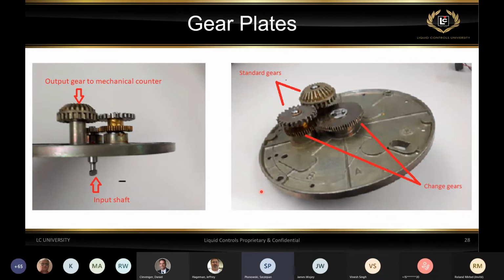If we look at a very simple gear plate picture, the gear plate, again, is a plate with a set of gears. On the bottom of that plate, you're going to see an input shaft, and that input shaft will generally engage with an adjuster, or some people call it a calibrator, micro adjuster. Then you have a set of gears that creates a specific output speed, and then you have an output gear, this little bevel gear, and this bevel gear will be engaged in most cases directly with the counter, with a similar bevel gear on the counter. Now, a gear plate has 2 gears. Again, in general, there are standard gears. That's the bevel gear, and you're going to see this silver gear. No, you can't see that part, but it will have the number 25 on the top. Those are considered standard gears, and you're going to see them on every gear plate. And there are also change gears.